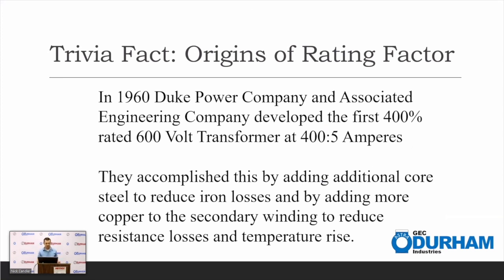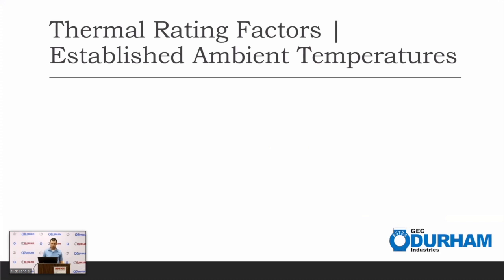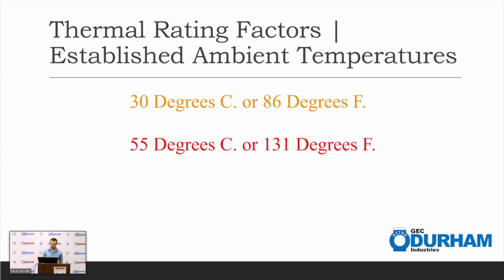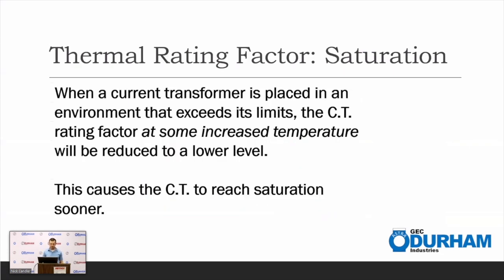Little trivia fact: it was Duke Power Company and Associated Engineering that developed the first 600 volt class transformer at a ratio of 400 to 5, with additional core steel to reduce iron losses, and by adding more copper to the secondary winding to reduce resistance. So yeah, thermal rating factors. We refer to it casually as rating factor, but it is actually thermal rating factor. The established temperatures are 30 degrees, 55 degrees, and 85 degrees.